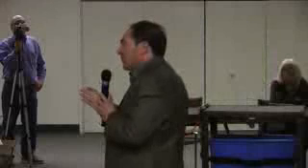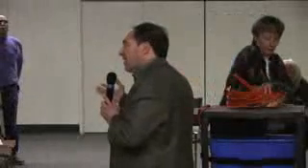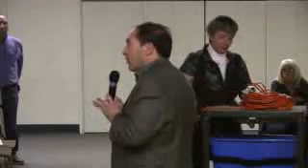In all seriousness, the training we did made a difference, even though we never had that specific event. And when we do training, we simulate things as much as we can. Obviously, we're not going to shut off San Diego to see how fast we can turn it back on. We've done that on paper. And on paper, it said that it could take us as long as 24 hours. And a big concern was, as you start bringing back your system, our 2 first priorities were to bring back energy to the power plants to start them, and to bring energy to the hospitals. So, the two priorities.